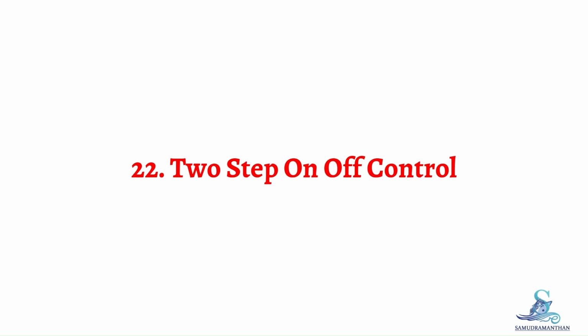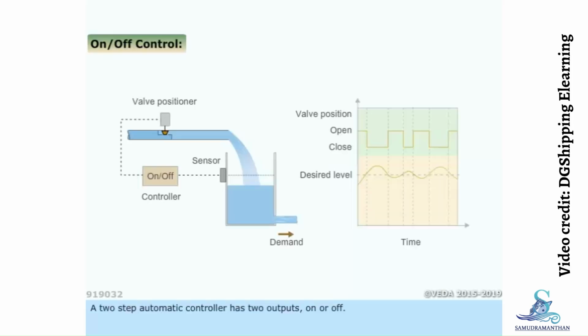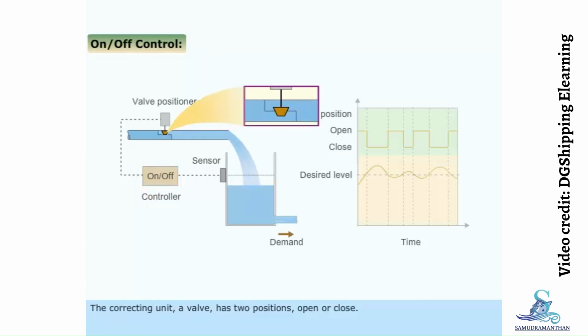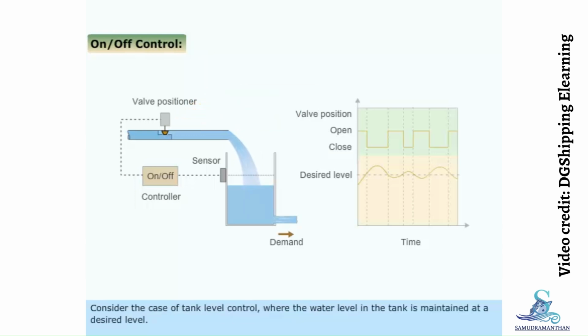Topic 22. Two-step on-off control. A two-step automatic controller has two outputs, on or off. The correcting unit, a valve, has two positions, open or close. Consider the case of tank level control, where the water level in the tank is maintained at a desired level.